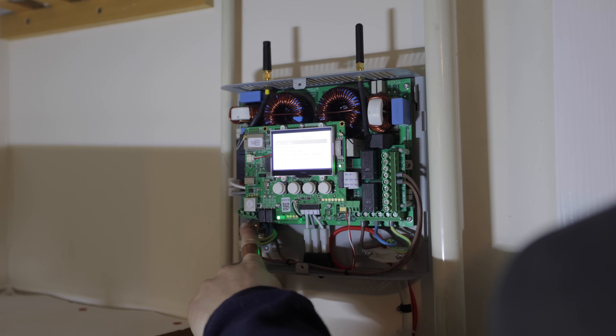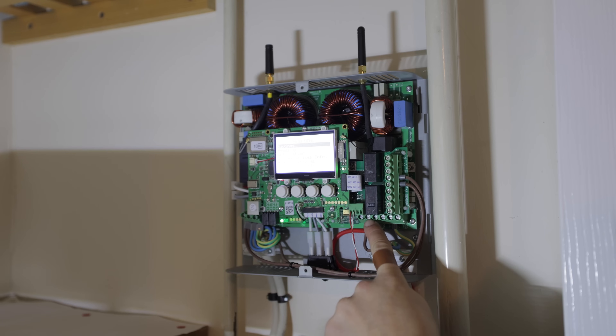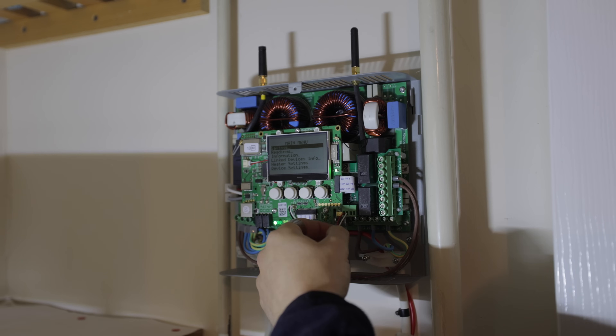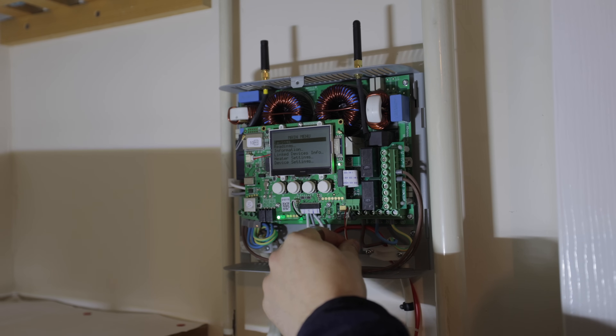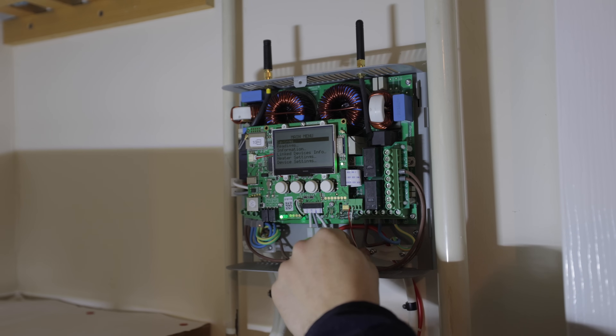Inside the eddi we've got our main supply and our load connections. You can actually install two loads onto this — say you've got two immersions, you can have immersion one and immersion two. There are also two connectors for a temperature probe, which goes onto the hot water tank, and on the menu it will show the actual current temperature of the tank.